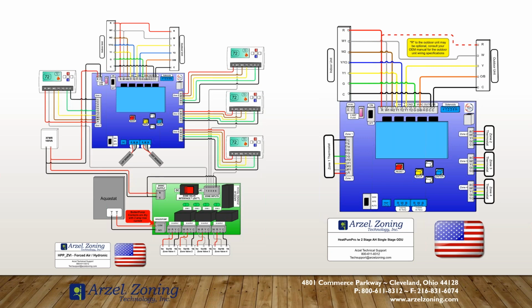Zone 1 thermostat calling opens every single damper in the entire system, and it conditions the building as a whole. So what that would be popular for is a commercial application where you just want non-programmable thermostats at zones 2 through 8. Zone 1 is programmable so that when you have a timing control, a timing relay at a certain time of day would close, everything would revert to the program built into zone 1, ignoring zones 2 through 8. Every damper would open, the building would maintain based on the zone 1 thermostat program.